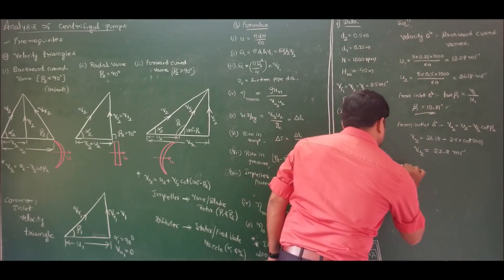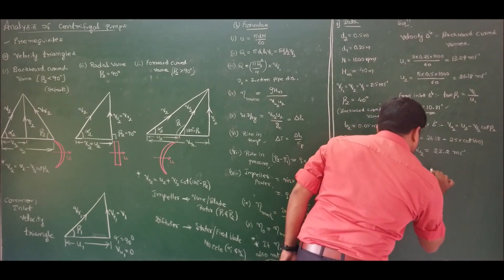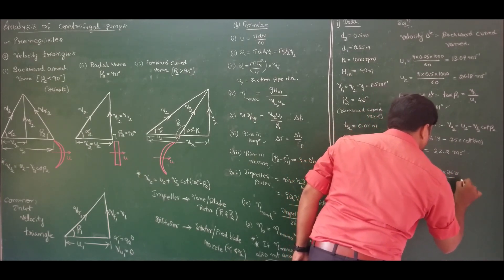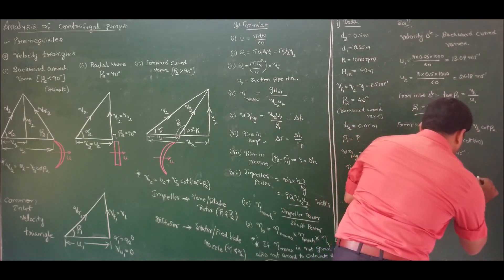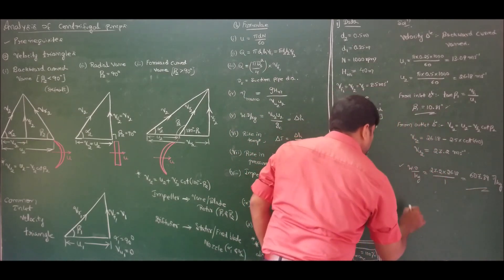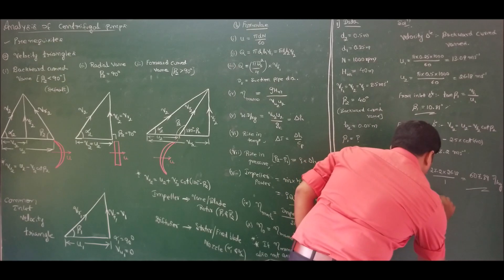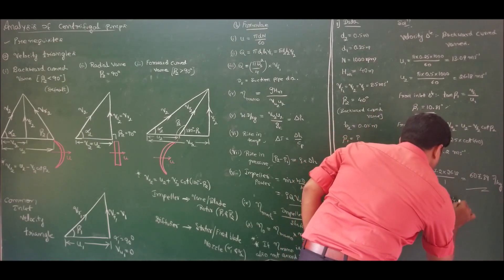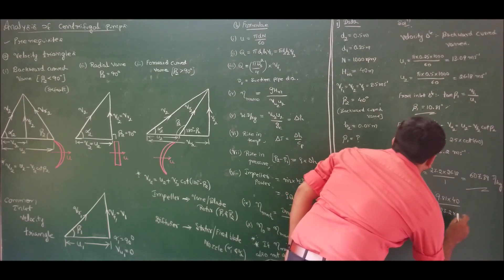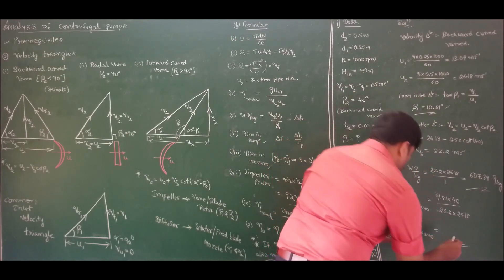Therefore work done per kg equals Vu2·U2 = 23.2 × 26.18 = 607.39 joules per kg. Next, we calculate manometric efficiency. Manometric efficiency = g·Hm / (Vu2·U2) = 9.81 × 40 / (23.2 × 26.18) = 392.4 / 607.39 = 64.6%.